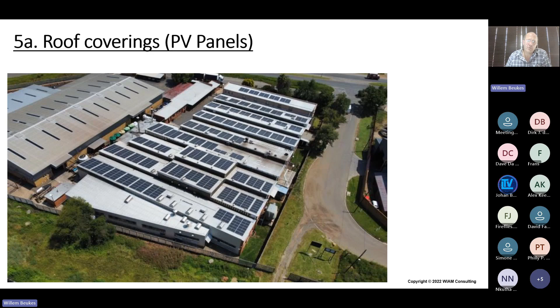Also very important is the layout of these installations, giving access routes and walkways, showing where the panels are located on the roof. When responders react to a fire, there should be a copy of these layouts at the reception of the building, so that the responders know where the panels are located on the roof, and the access routes to these panels, to be able to respond and switch off these panels, either by disconnecting the DC cables or by means of firefighting, whether you use a PV stop or other measures to stop the fire on existing systems.